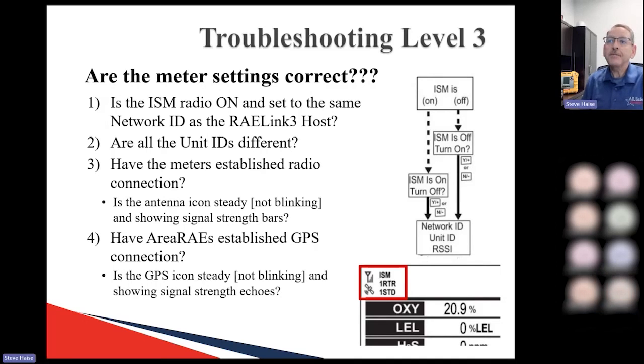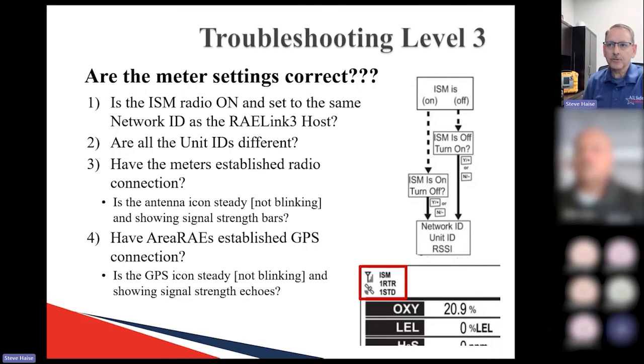Number 3, have the meters established radio connection. This is a real easy troubleshooting step because it's a visual. If you look in the top left-hand corner of your AreaRAE, you'll see this little antenna icon with the bars next to it. As long as that icon is burning steady, meaning it's not blinking, and you see the signal bars, that's a good sign that it is communicating with the RAELink3.